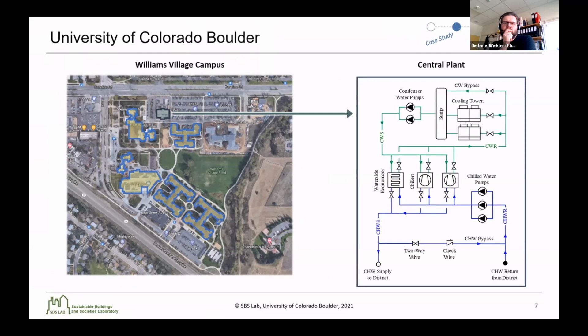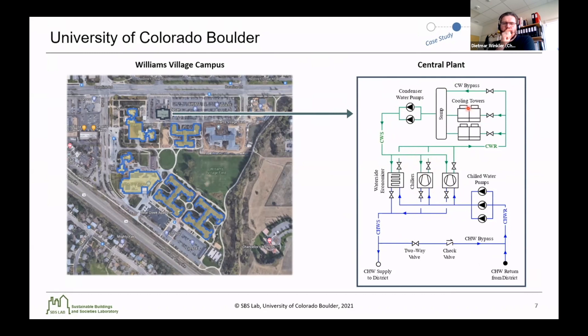For some of the details, I've included a schematic of the central plant. This plant has two water-cooled chillers connected in parallel with the water-side economizer, so either the economizer can run or the chillers can run, but both cannot run at the same time. In blue is the chilled water side — the cooled water distributed to the rest of the district — with variable speed chilled water pumps and a bypass loop that maintains minimum flow rate through the chillers. The condenser water side shown in green rejects heat from the chillers and water-side economizer, with two cooling towers, a bypass loop, and two constant-speed condenser water pumps.